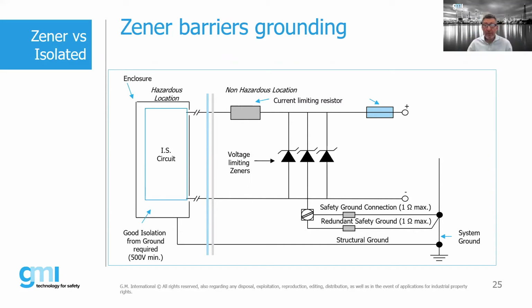When you are talking about these numbers, which standards are we talking about? That's the IEC standard, the -14. Yes. In the USA, what standard are they typically applying? We follow the National Electrical Code, the NEC, in Article 504. Yes, 505 is the zone concept. Article 504 is for installations of IS. What that translates into in AWG, I don't remember right now. It's okay, but it is within the NEC. And the CEC also has a similar passage within the Canadian Electrical Code.